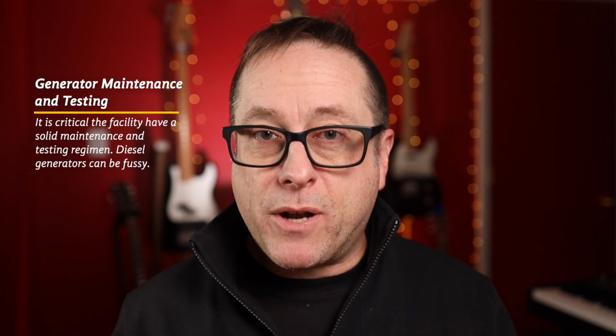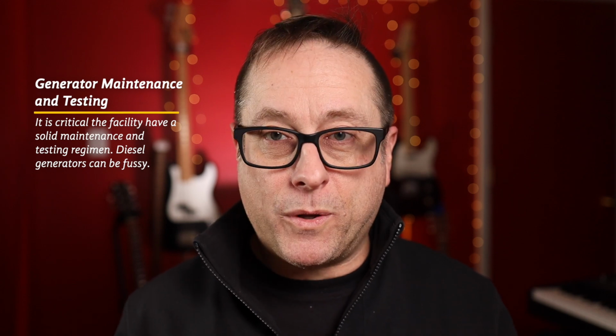Ask about their maintenance and testing procedures. Diesel generators need to be tested frequently. In cold weather, they need to be started on a regular basis so that you can be sure they will start when you need them to. In very cold winters, we used to run our generators every single day to make sure that they were going to work in an emergency situation. Burning fuel also helps with keeping the fuel free from fungus and mold. Diesel can be tricky to store over a long period of time, and you have to manage to these things.